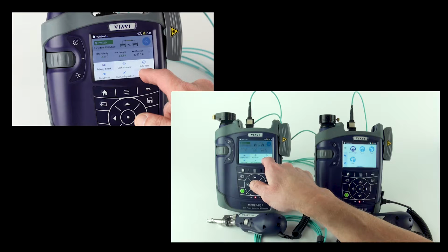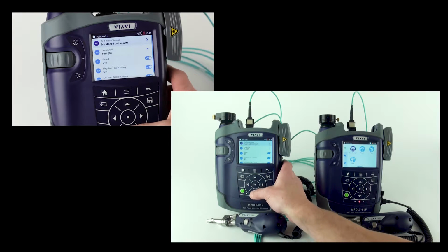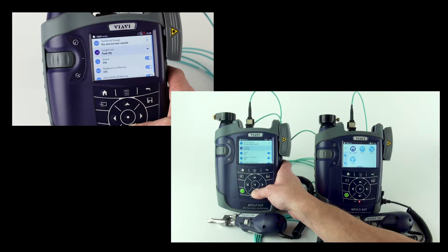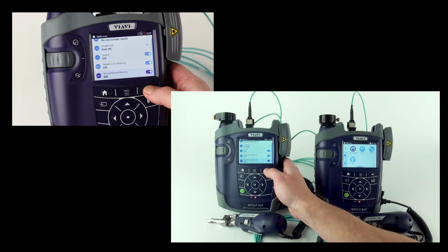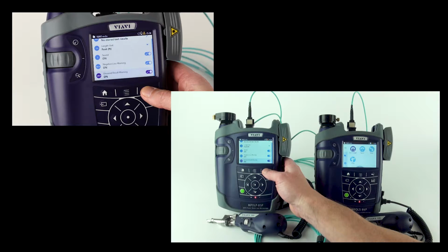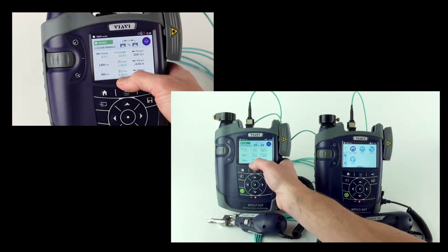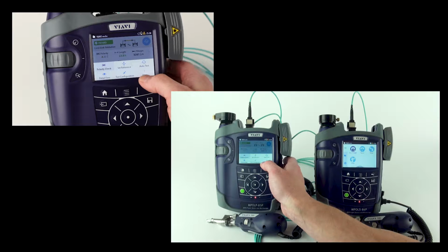There is a More button which allows you to set up some things in terms of feet or meters, sound on and off, and whether you want a negative loss warning on or off - that default is on, and we recommend you leave it on. You can also set an unsaved results warning, which means if you leave the screen where your test results are, it will prompt you that you haven't saved it, preventing you from losing results. But if you're just testing and don't need to save anything, you may want to turn that off. That's all under the menu, under More.